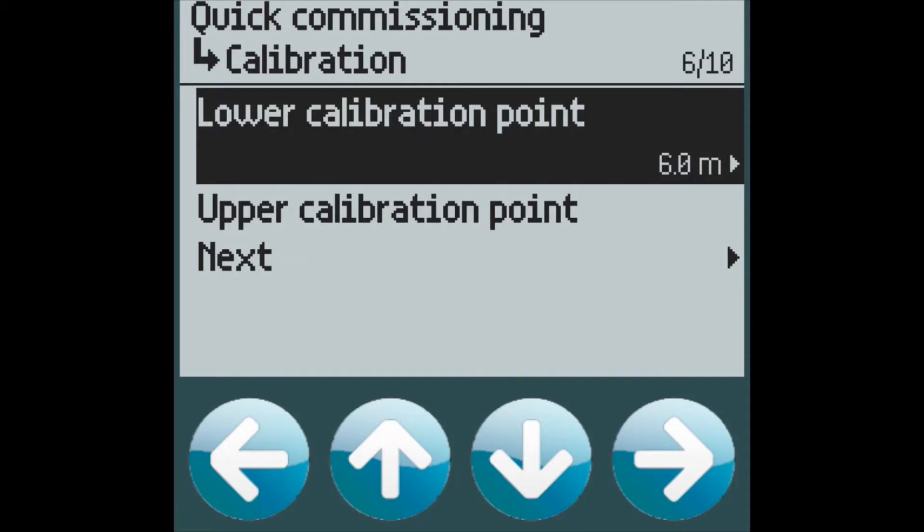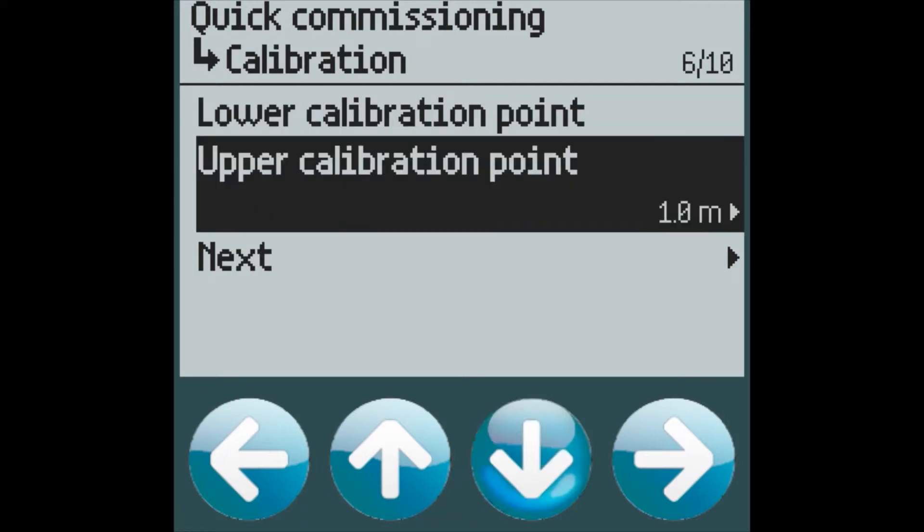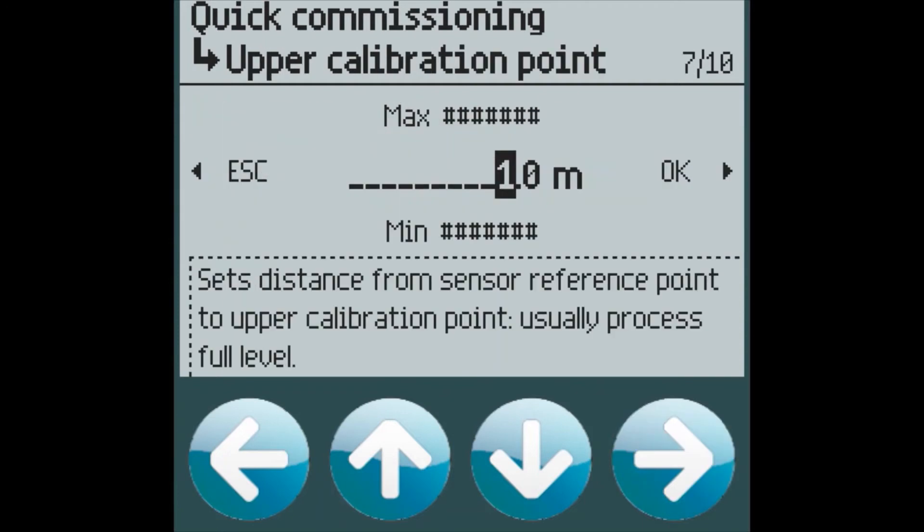The lower calibration point is set at 6 meters, and this is the distance from the sensor to the bottom of the tank. The upper calibration point is set at 1 meter, and we will change this to be 0 meters from the sensor to the top of where we will be measuring material.